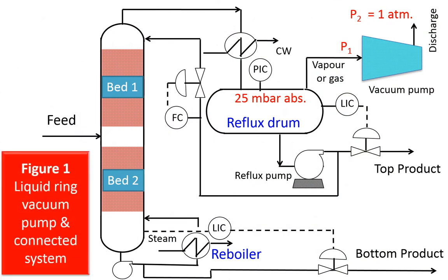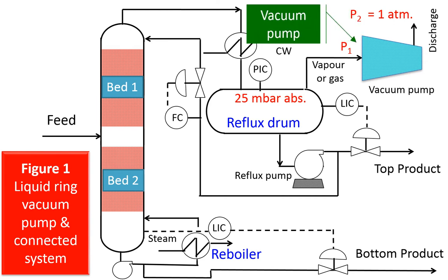This figure illustrates a vacuum pump connected to a distillation system. The liquid ring vacuum pump is connected to the reflux drum because it serves to remove the non-condensables and vapors from the reflux drum at sub-atmospheric pressure, compresses them, and discharges to atmosphere.